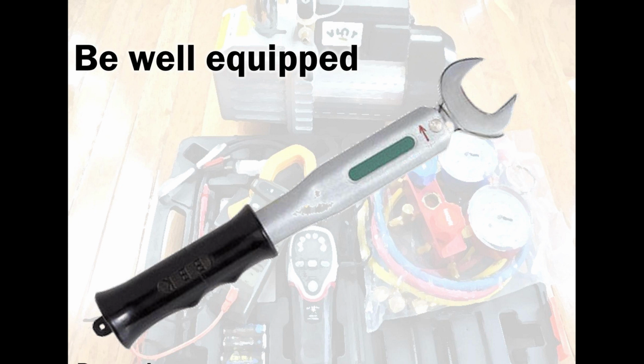Even when you're tightening the wheel on your car, always use a torque wrench. Insist that your mechanic use a torque wrench, or that tire is going to come out flying and hit somebody on the highway. It's the same story here. If you don't tighten it well, or if you overtighten it, you're going to cause a leak. The nuts are going to freeze, and when they freeze, they're going to crack. And when they crack, that's how you get completely out of refrigerant. I have seen it firsthand. I have seen it with my own eyes.